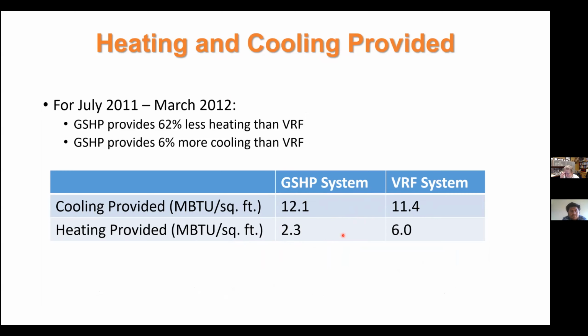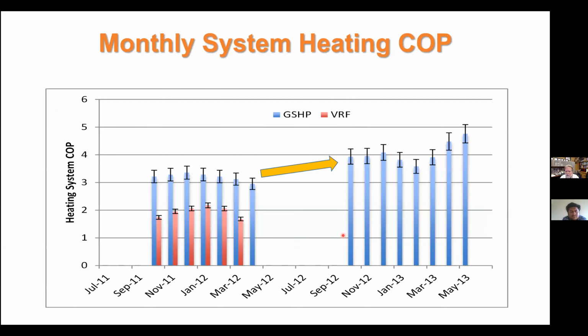So the way we typically characterize the performance of the system is the coefficient of performance, in this case integrated over time. Again, I'd probably call this a performance factor now. It's the ratio of what you're getting, the heating, divided by what you're paying for the electricity. And you can see that the ground source heat pump system compared to the VRF is roughly a COP of 3 over the season, and the VRF system's roughly 2 over the season. So it's significantly better for heating. Another interesting aspect is this change from winter 11-12 to this winter: you see that the GSHP system goes up from about 3 to about 4. And we're going to come back to why that is a little bit later.